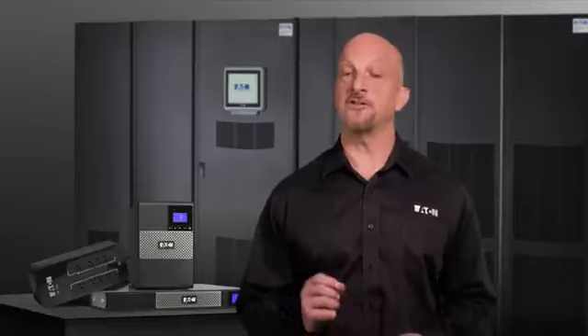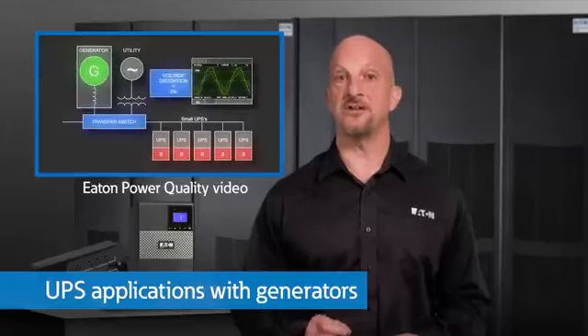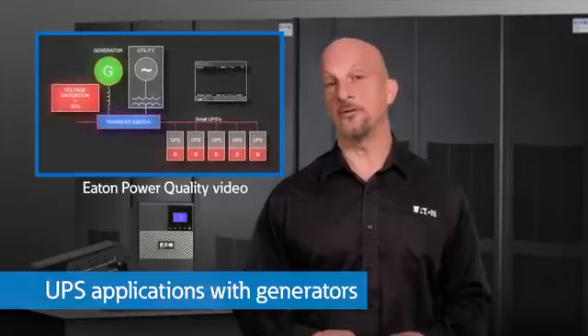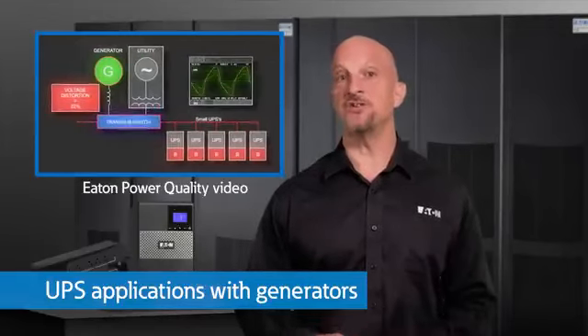Note that if you buy an offline or line interactive UPS and the supply voltage is poor, which often happens on a weak utility source, or when you're running on a generator, the UPS may stay on the battery and drain the battery because the sensing doesn't like the wave shape or level of the source voltage. In this case, you may drop the load if the battery runs out of charge.